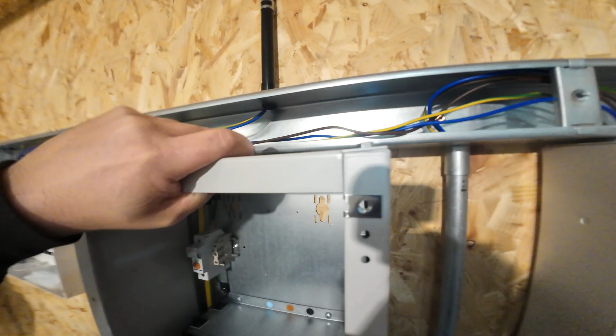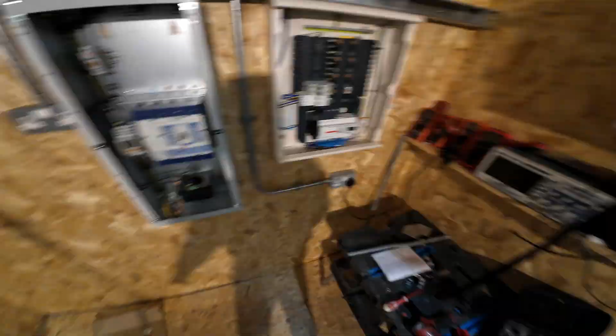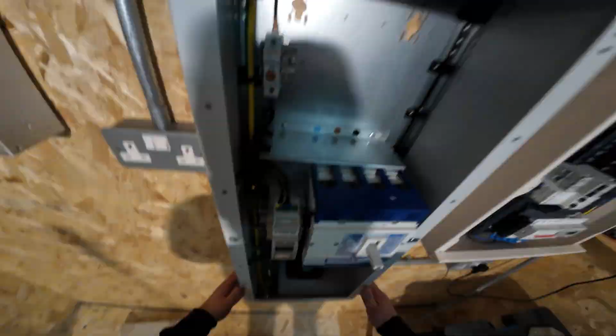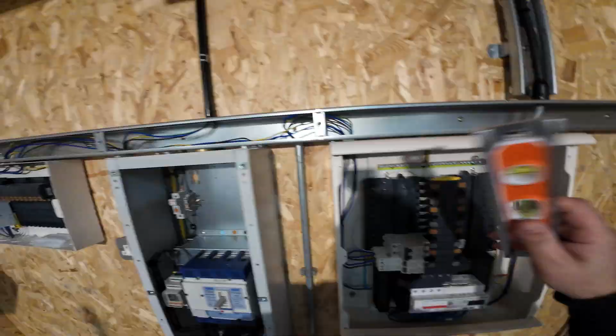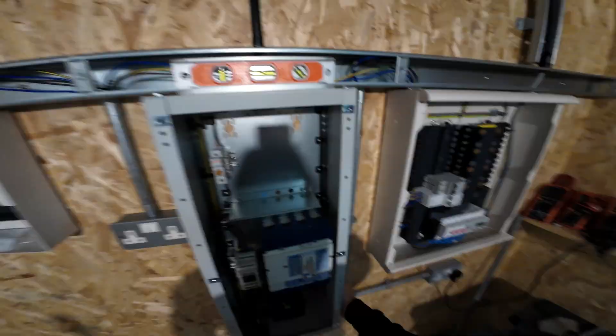But if you ever are making holes into containment, make sure you are protecting your existing cables and not drilling into them. You see here we've got our female nut on the inside here, so it's going to protect those threads from any snags rather than just using a normal fastener on the inside. So we're not going to snag any edges of the cables.